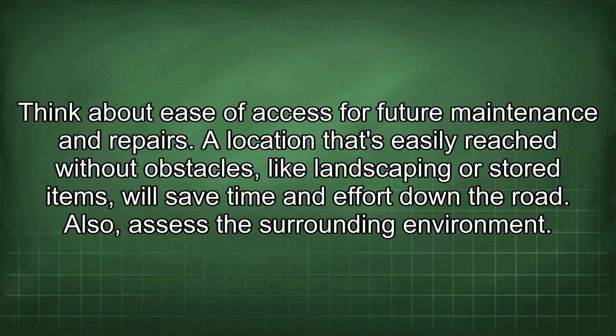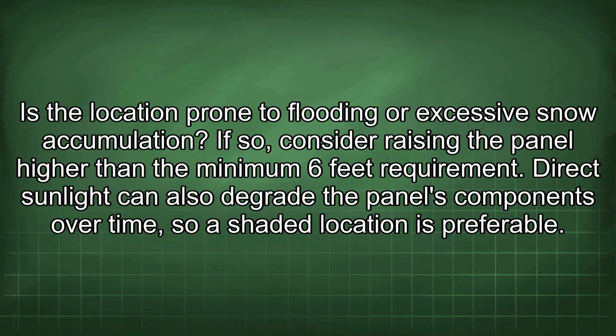A location that's easily reached without obstacles, like landscaping or stored items, will save time and effort down the road. Also, assess the surrounding environment. Is the location prone to flooding or excessive snow accumulation? If so, consider raising the panel higher than the minimum 6 feet requirement. Direct sunlight can also degrade the panel's components over time, so a shaded location is preferable.